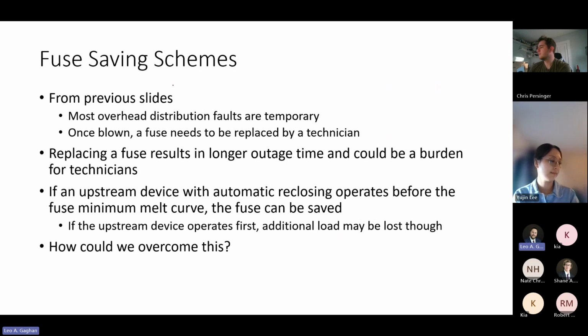So if an upstream device with automatic reclosing operates before a fuse minimum melt, the fuse can be saved. It's called fuse saving. If the upstream device operates first, additional load may be lost though. So any ideas how we could overcome this? Well, we had a slide for it early on. It's a fast curve and a slow curve.